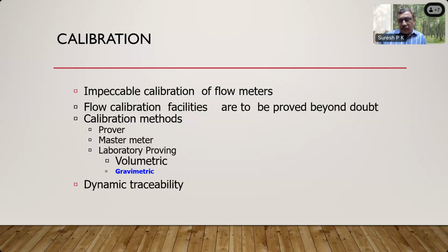Everywhere similar systems are available, and you take a meter which is calibrated here, take a meter which is calibrated there, and compare the results between these two, which is mandatory for getting the NABL accreditation nowadays. So NABL accreditation standards mandate this kind of comparison, international intercomparison or national intercomparison, for obtaining traceability. For obtaining the NABL accreditation, which ensures dynamic traceability. This is applicable for any kind of measurement, not only flow measurement. All flow measurements need to have dynamic traceability because the system can affect the accuracy in many ways.